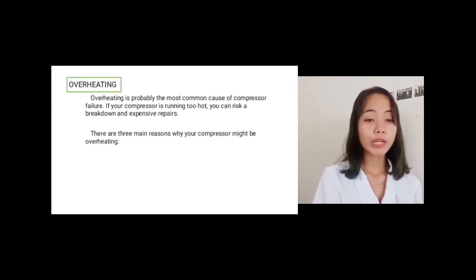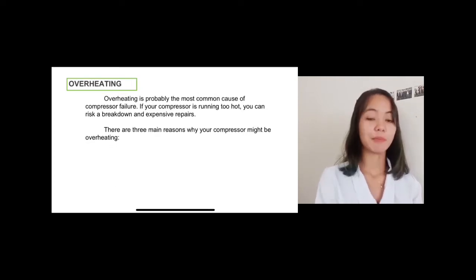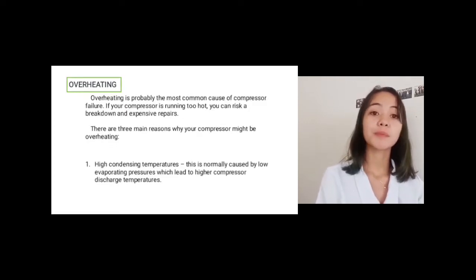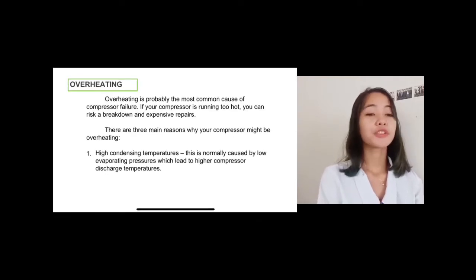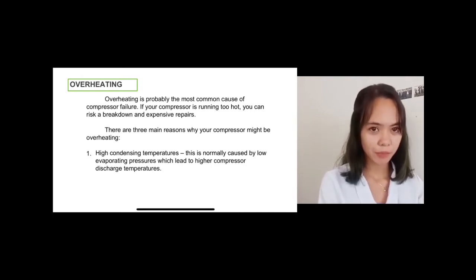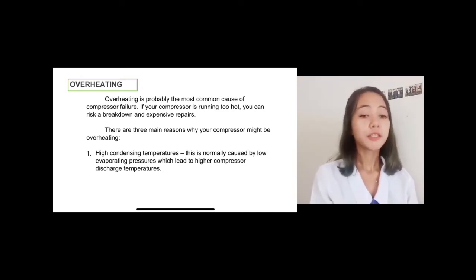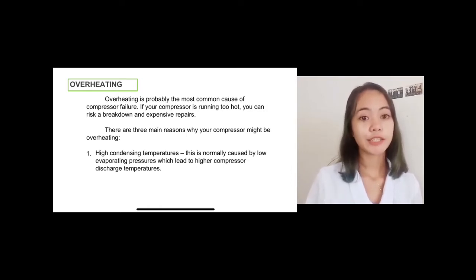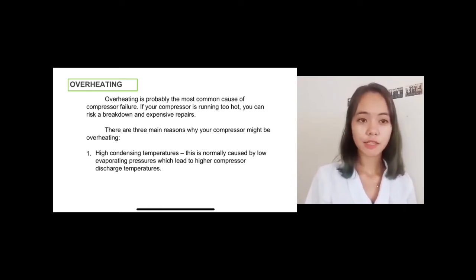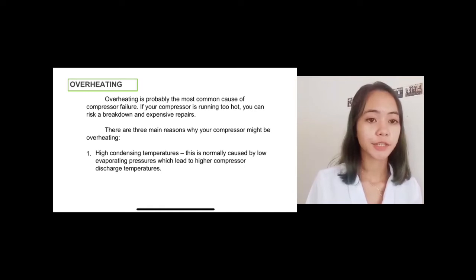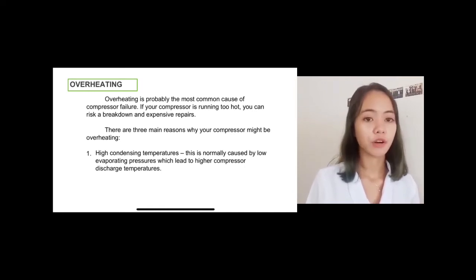And there are three main reasons why your compressors might be overheating. The first would be the high condensing temperature. This is normally caused by low evaporating pressures, which lead to a higher compressor discharge temperature. Possible causes include dirty condenser, high temperature condenser, fan motor malfunction, insufficient airflow to condenser, overcharged refrigerant, and wrong refrigerant.